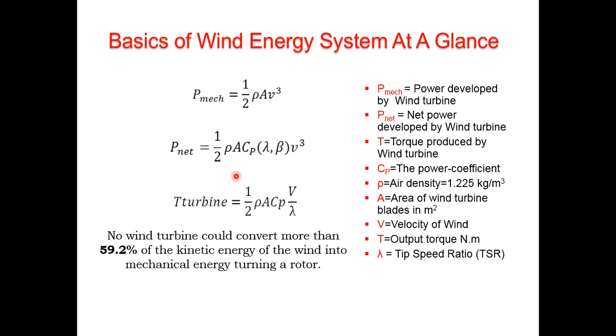The power available from the wind — the mechanical power — is given by one-half rho A v-cubed. If we multiply this by the power coefficient Cp, we get the net shaft power. Here Cp is a function of lambda and beta, where lambda is the tip speed ratio and beta is the blade pitch angle. This also gives the torque equation of the wind turbine.